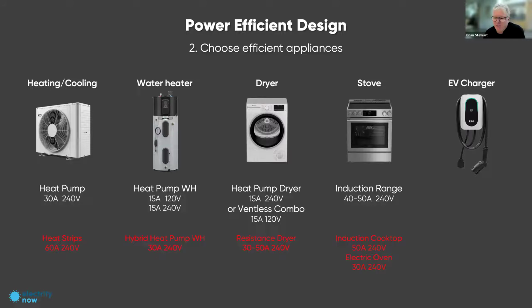In general, you're going to need a 40 to 50 amp circuit for an induction range. A lot of them run on 40 amps—ours does—but some require 50, so you want to check that. The thing you want to avoid, if you can, is splitting your range into a separate cooktop and oven. If you avoid that, you save another circuit, because a separate cooktop and oven setup needs its own 50 amp circuit (or 40 for the cooktop) plus another 30 amps for the oven. So you'd be adding a circuit that you could avoid by using a range instead.